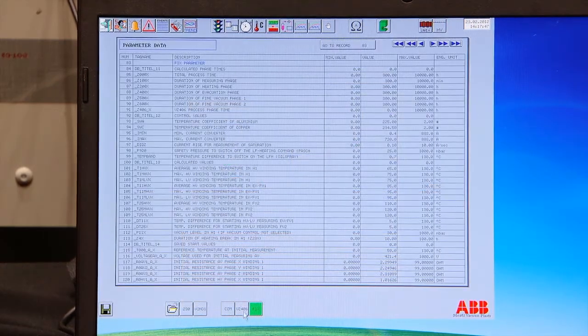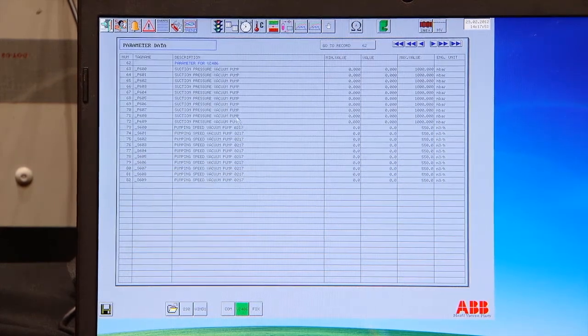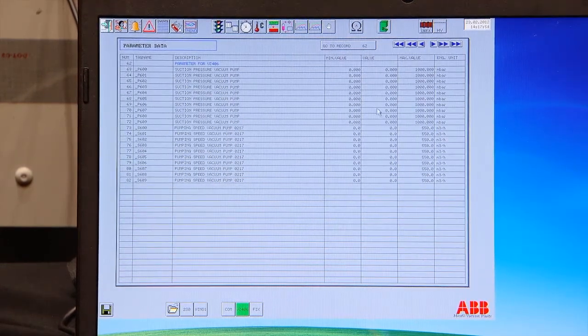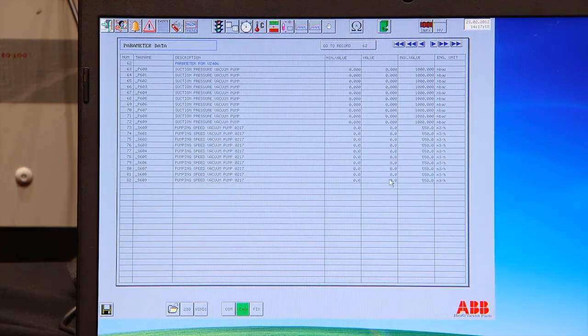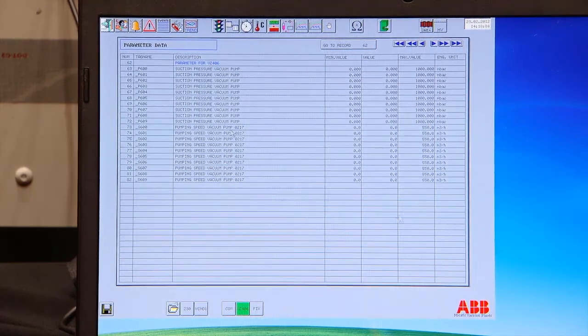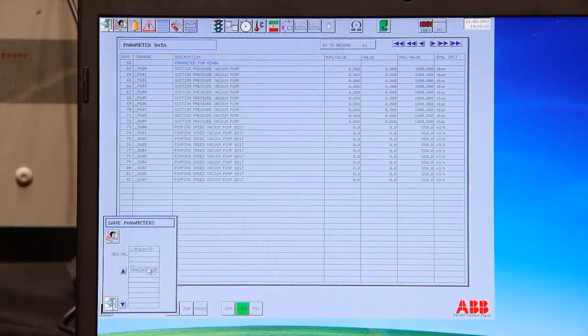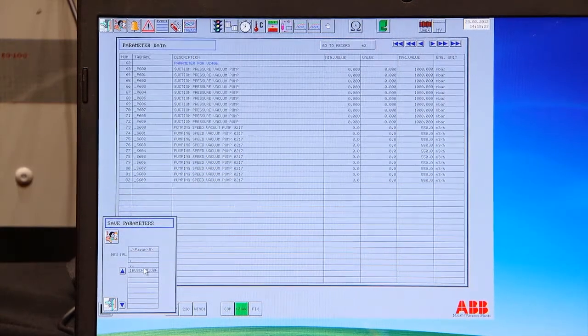On this page, the parameters for the VZ406, you have the suction capacity here. You see everything is 0 at the moment. Here the values from this reading will be filled out. Then you have the suction pressure for the vacuum pump and the corresponding pumping speed. You can save this and reference back to it. You can save it here and call it factory setup.